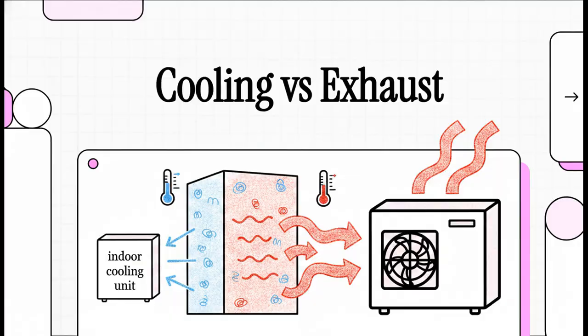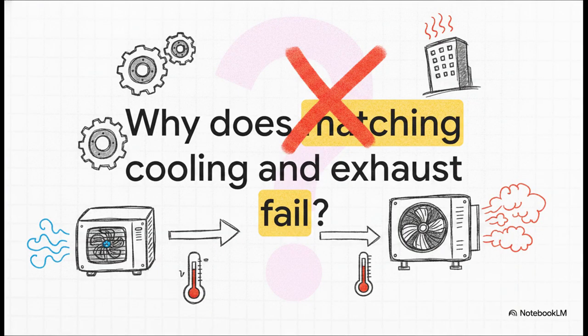Let's get into it. Now, if you buy a 100 capacity indoor cooling machine, why does pairing it with a 100 capacity outdoor exhaust system lead to total, catastrophic failure? I mean, matching a 100 to a 100 seems like perfect common sense, right? You pull 100 units of heat out of a room, you should just need a system that throws 100 units of heat outside. Seems completely logical.